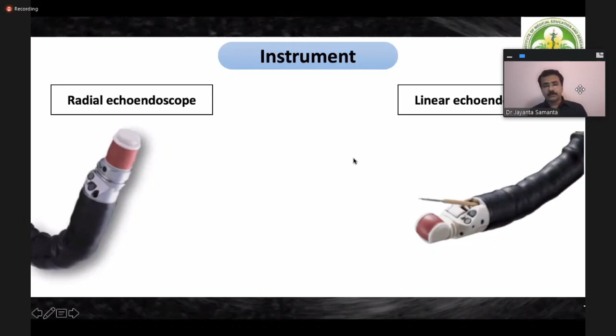Nowadays, we have two kinds of basic instruments. One is the radial echoendoscope and the other is the linear echoendoscope. What is the difference between the two? A radial echoendoscope was the first generation of echoendoscopes of the modern times, where the ultrasound transducer gives an imaging plane of a scanning image of 360 degrees. So basically we can get a 360 degree scanning image of the ultrasound.